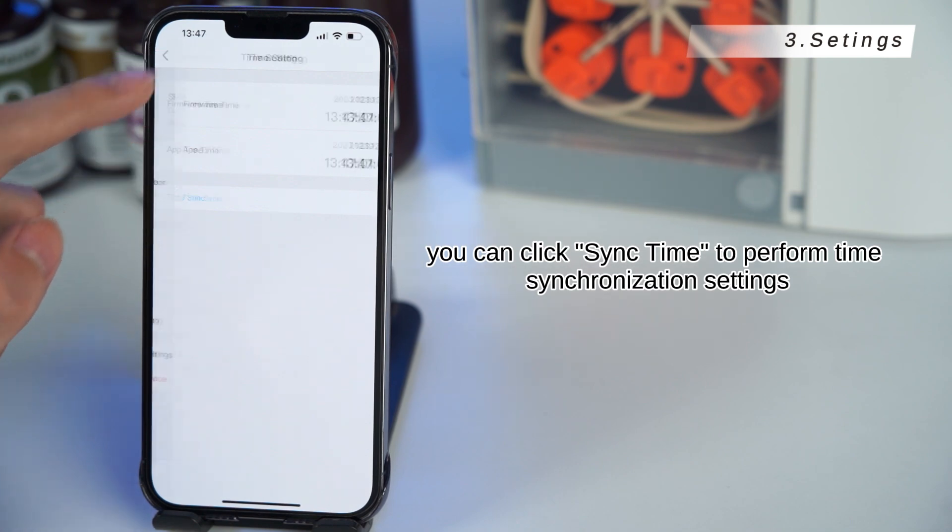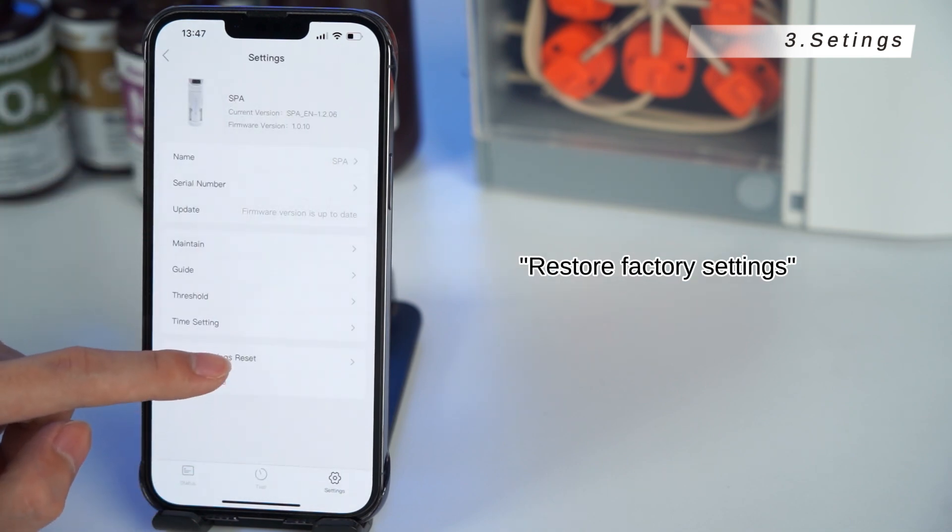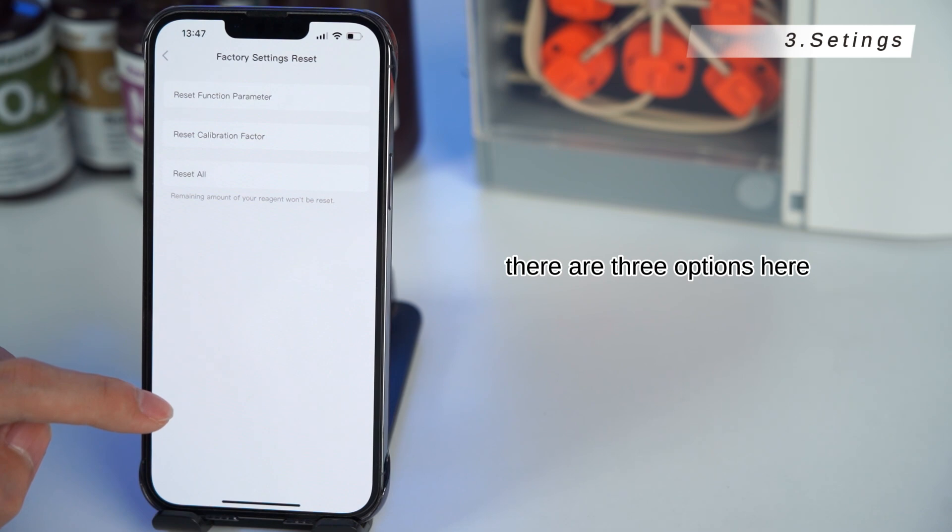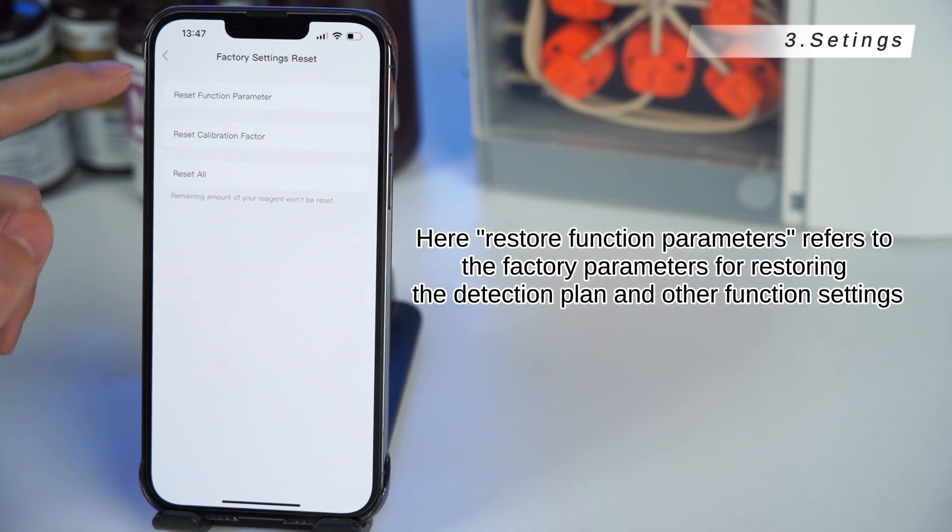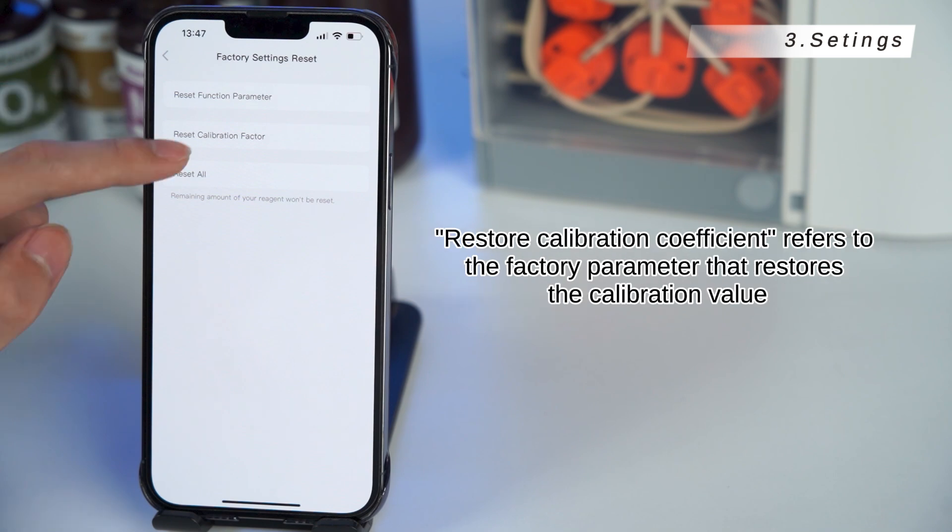Restore factory settings, there are three options here. Restore function parameters refers to the factory parameters for restoring the detection plan and other function settings. Restore calibration coefficient refers to the factory parameter that restores the calibration value.